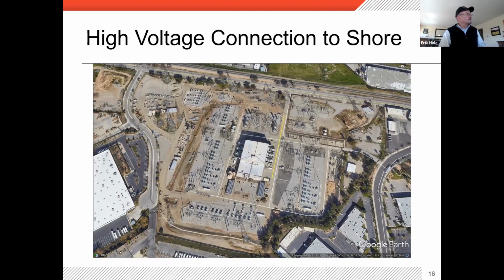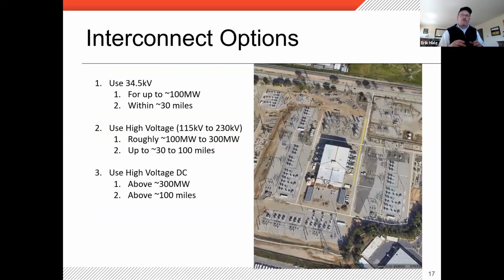So this is my summary slide for interconnections for the portion that is at sea and is going to go to the point of interconnect, presumably the AC or DC backbone that Bill had been describing. For up to 100 megawatts, and if you're within 20 to 30 miles of shore, you actually don't even need a collection substation — you could take this directly to shore. That would be the easiest way, but you're tremendously limited, and 100 megawatts is probably stretching it on the high end.